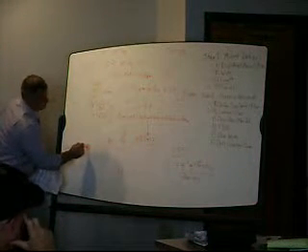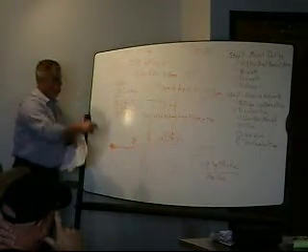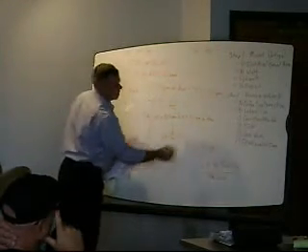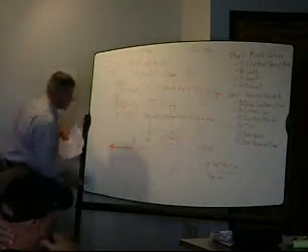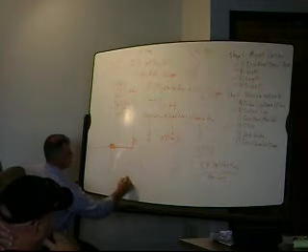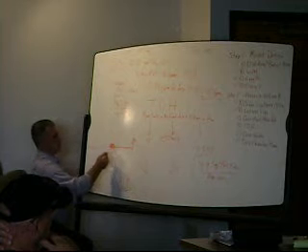is your 4.55. That is the delivery head you want right here. Because at the end, I'm going to have friction, so I'm going to lose some before I get to the end. And that's why you have to build that into the pipelines. Elevation head, all that is from the pump, bottom of the tank, suction point, to here. How much elevation difference is there? That's all that is.